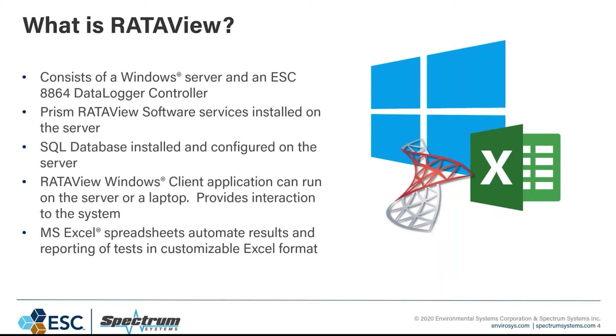There are a few RATAView software services installed on that Windows server. It's typically a rack mount server placed next to your analyzers in your rack, though that's customizable. Also on that server is a SQL Express database, which we install and configure for you. The third piece is the RATAView Windows client application, which is what you launch and interact with to run your tests, capture results, and save those. The fourth piece is the MS Excel spreadsheets used for results calculation and reporting.